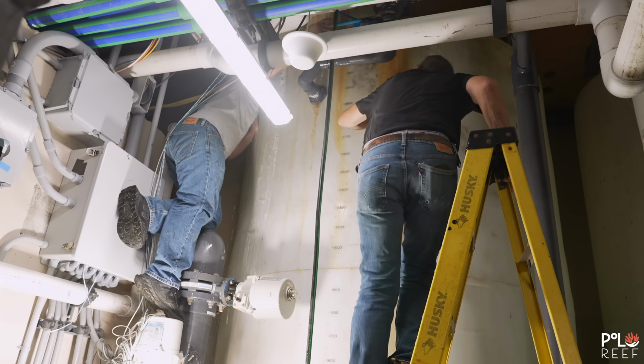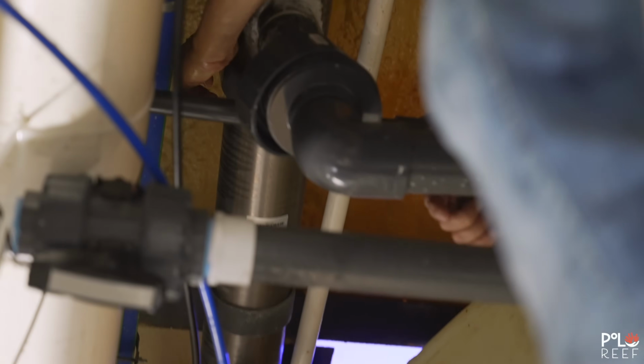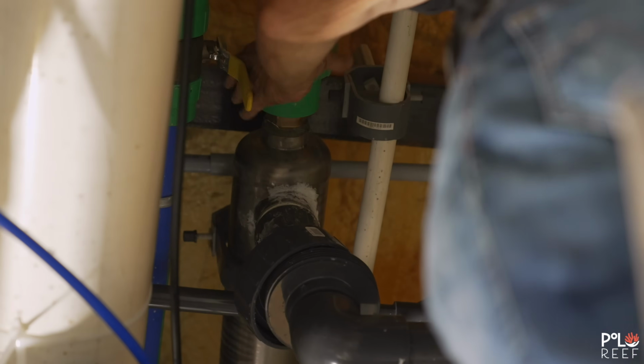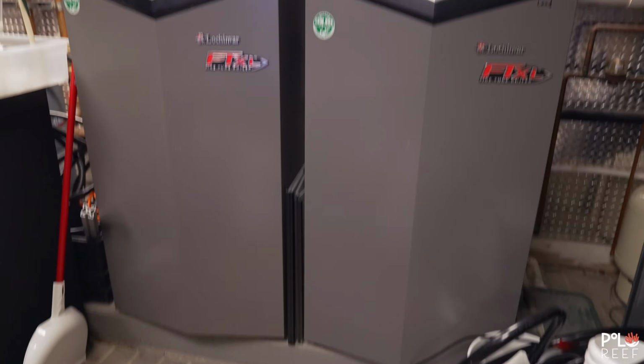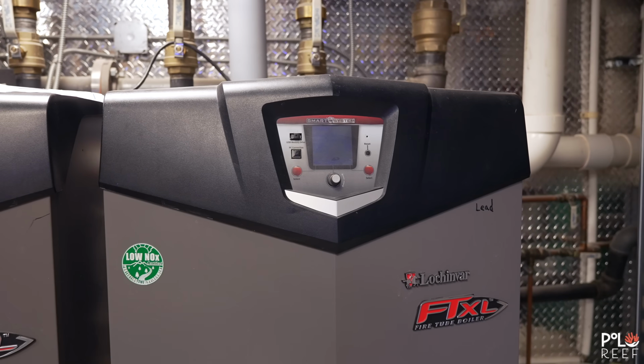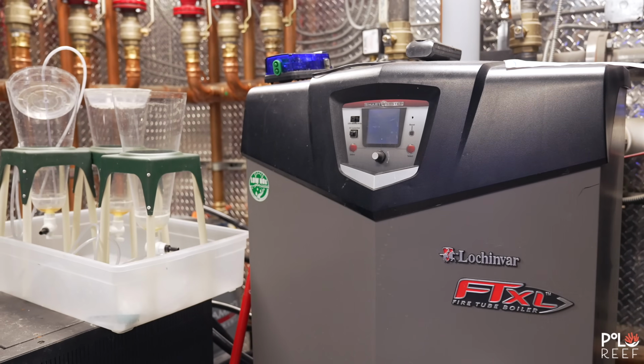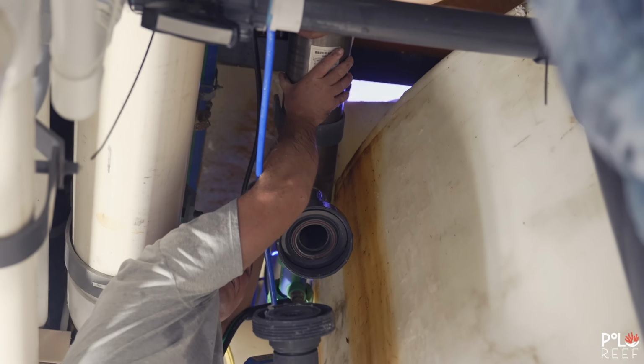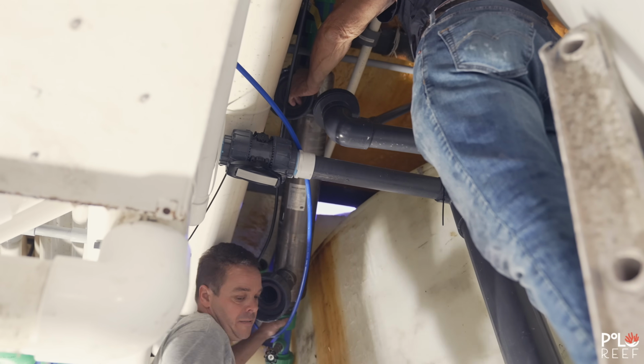So today we're continuing our search for the copper that's showing up on the ICP, that's moving from tank to tank. We are going to look at the heat exchanger on the saltwater mixing tower today. We're going to pull it out, pressurize it and see if there are any pinhole leaks in it, and see if the copper is possibly coming from the boiler water. After that, we are going to look at the mixing pump too and just check the shaft on that as well. Elevated levels of metals are never good for any reef system.